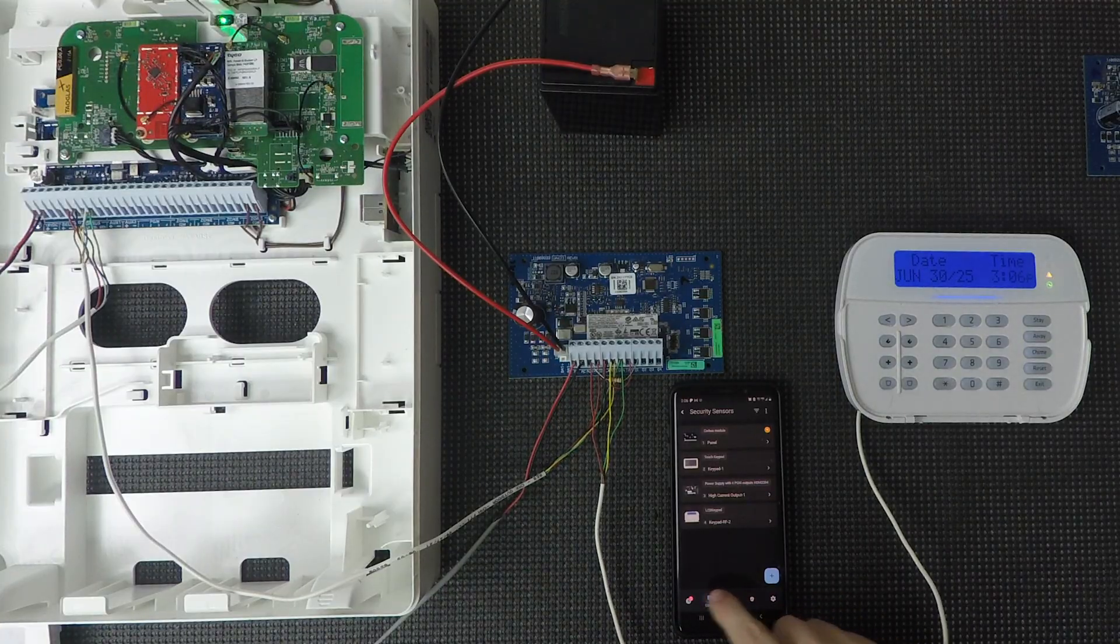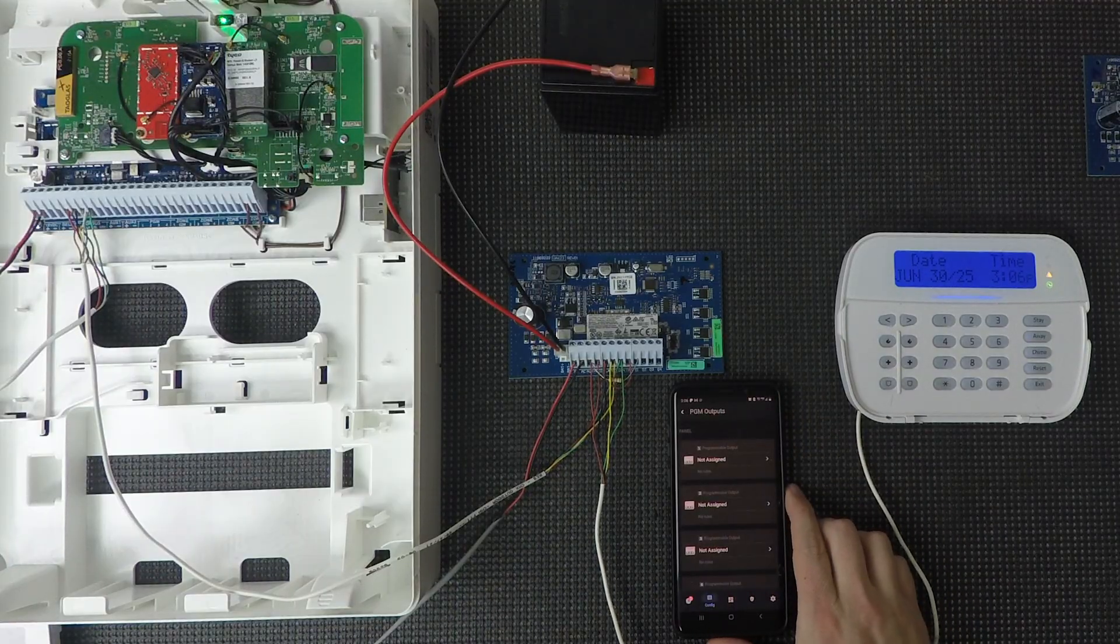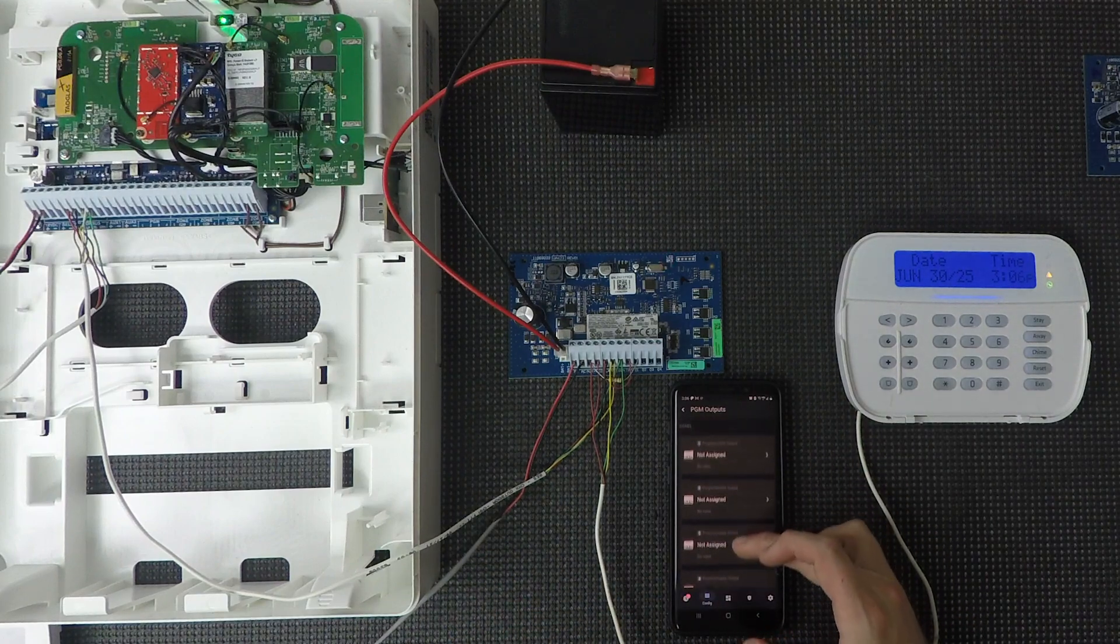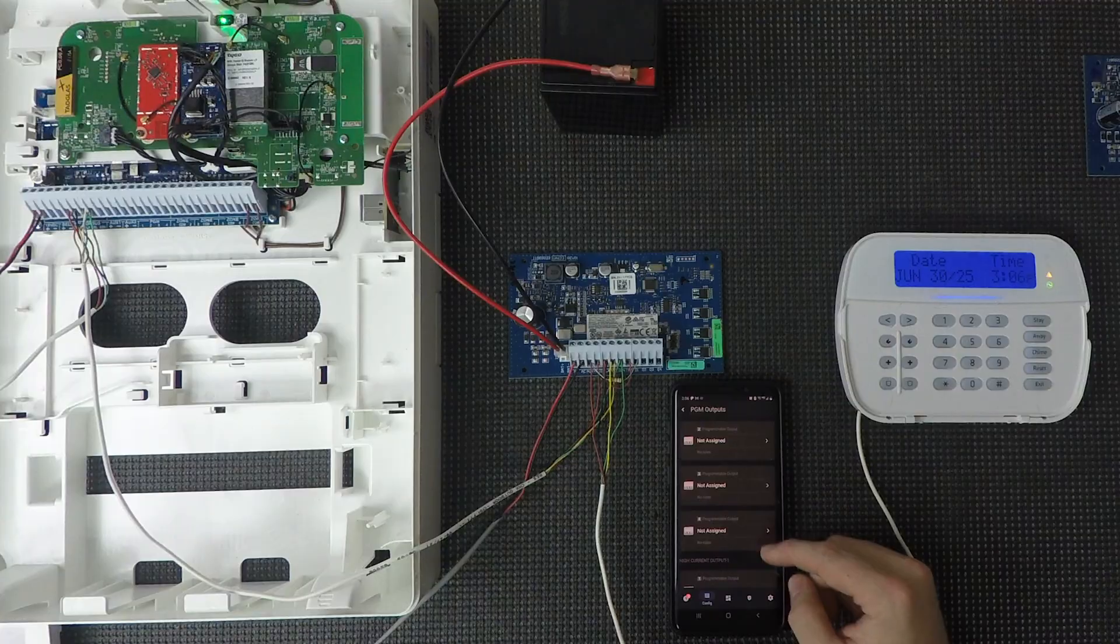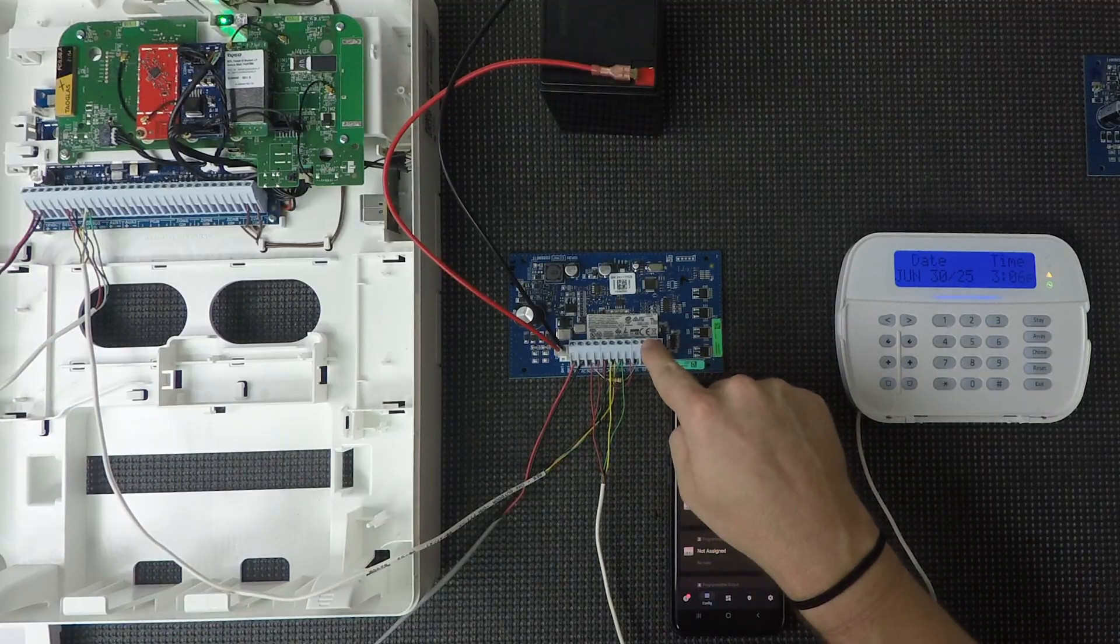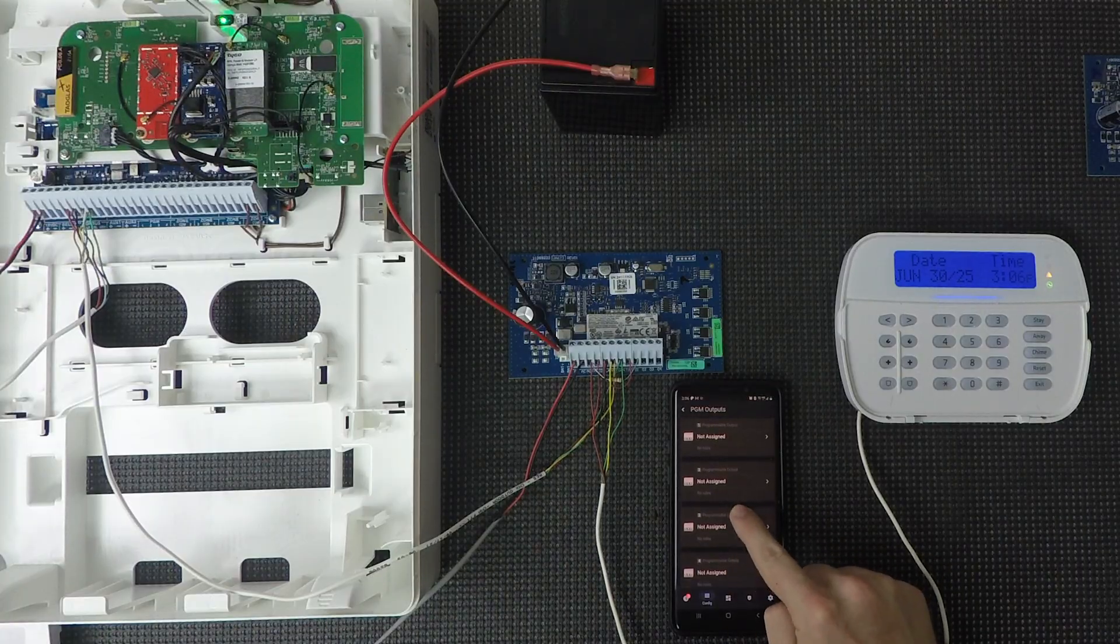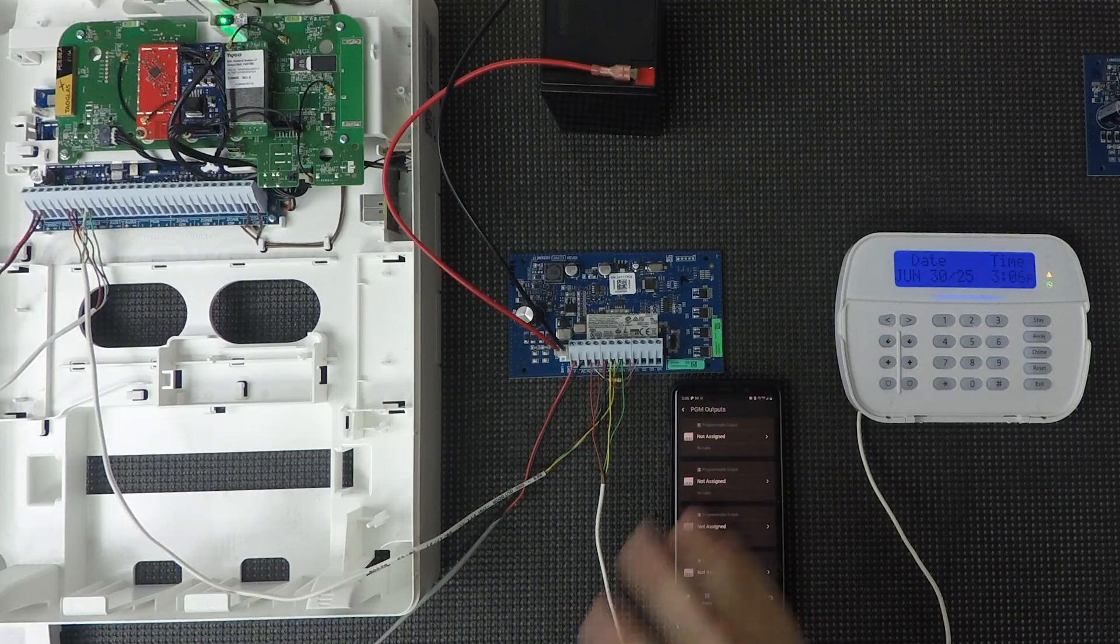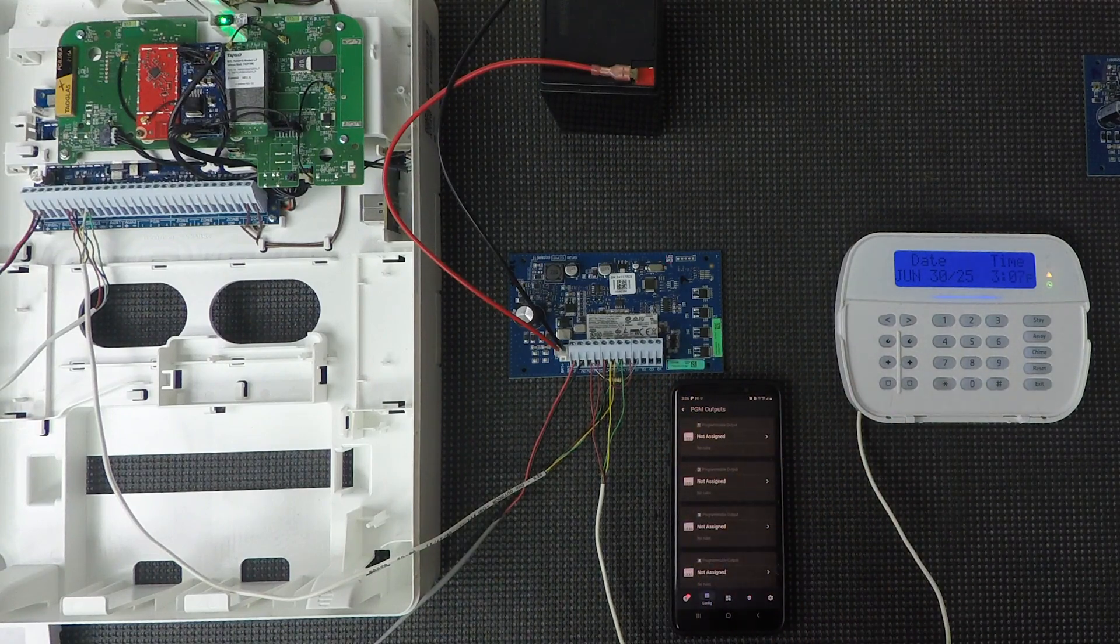So to do that, you'll click config, and then installation, devices, and then PGM outputs. So by default, like I said, you have four PGMs on the main board. So if you look through here, we see panel up here at the top, and then we have four programmable outputs right there. That's each of the four PGMs there. Now we have an additional high current output one, which is the name of this device in the system, and we have four additional programmable outputs here. So by default, none of them are set up to really do anything. So the only thing you've got to worry about if you're not using them right away is having that resistor on so that O1 does not show the bell circuit trouble.